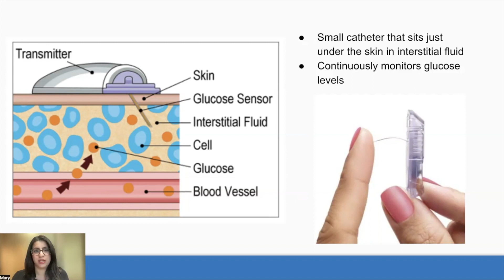One important thing to note is that a glucose reading from a CGM will have about a 5 to 15-minute delay when compared to blood glucose reading done via finger stick. This is the average time it takes from glucose in the blood to reach the interstitial fluid. When directly compared to a finger stick, the two readings should be comparable. You may note a larger discrepancy if the person's blood glucose is changing rapidly. However, if the accuracy of a CGM is questionable or during an acute episode, it is recommended to check a glucose via finger stick blood test.